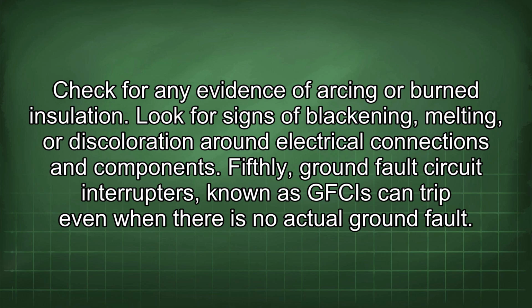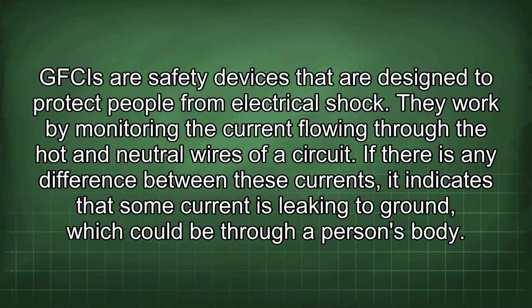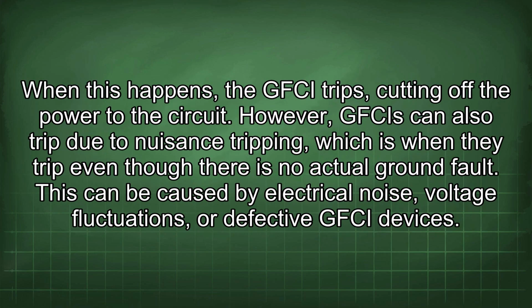Fifthly, ground fault circuit interrupters, known as GFCIs, can trip even when there is no actual ground fault. GFCIs are safety devices that are designed to protect people from electrical shock. They work by monitoring the current flowing through the hot and neutral wires of a circuit. If there is any difference between these currents, it indicates that some current is leaking to ground, which could be through a person's body. When this happens, the GFCI trips, cutting off the power to the circuit.